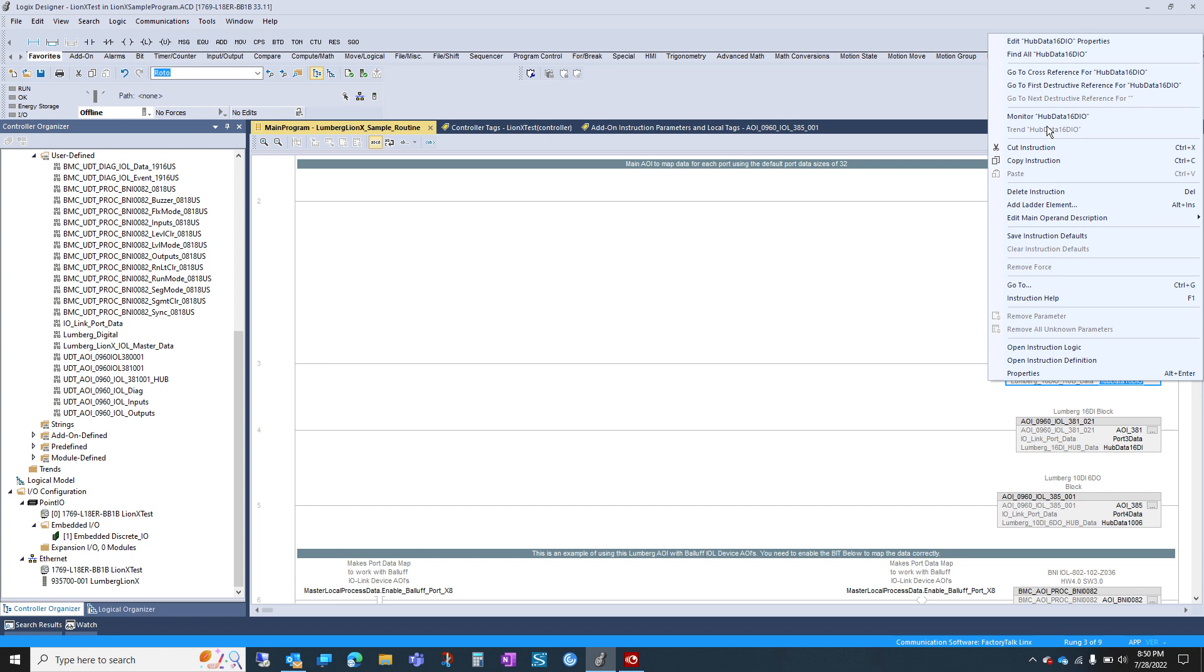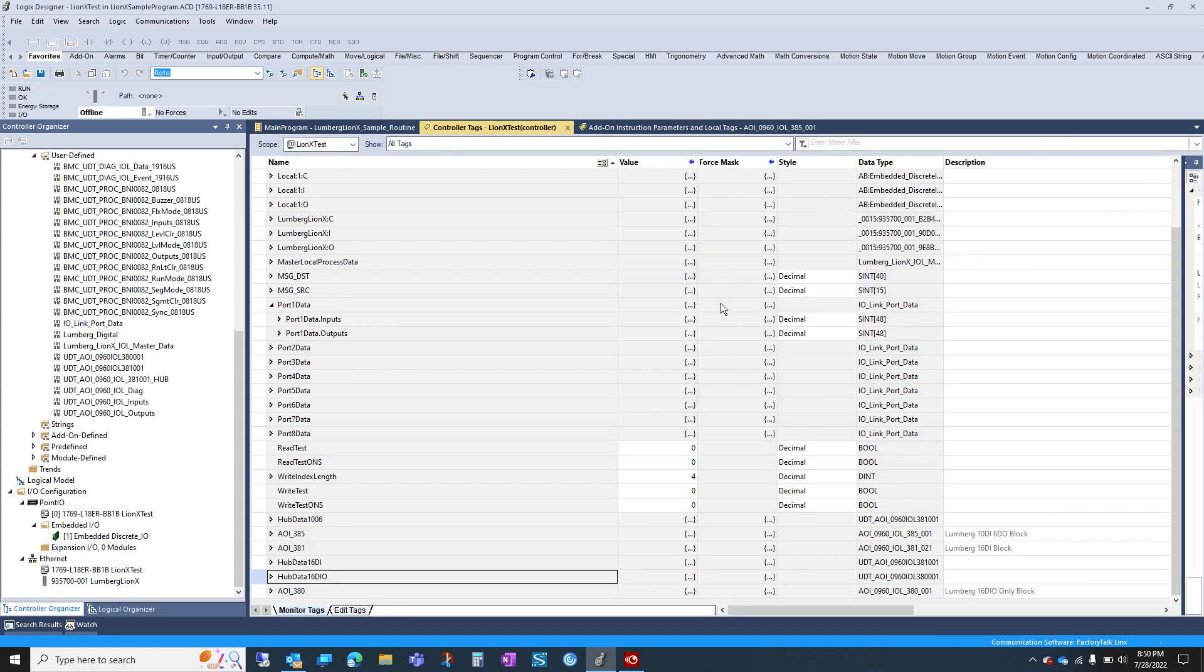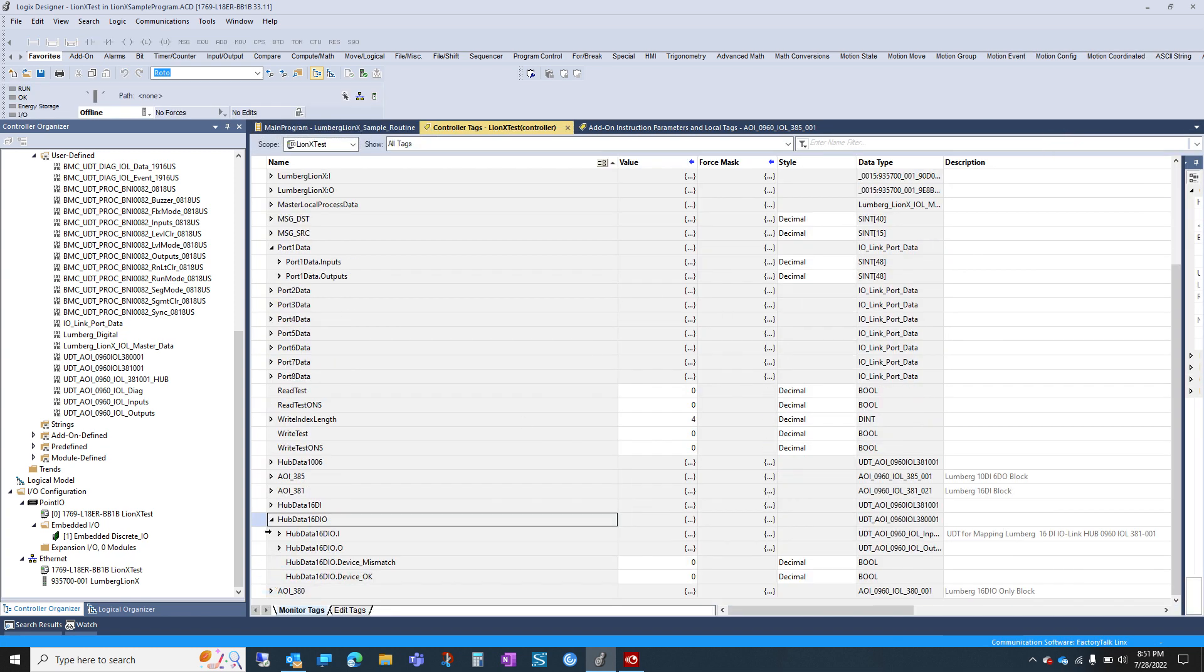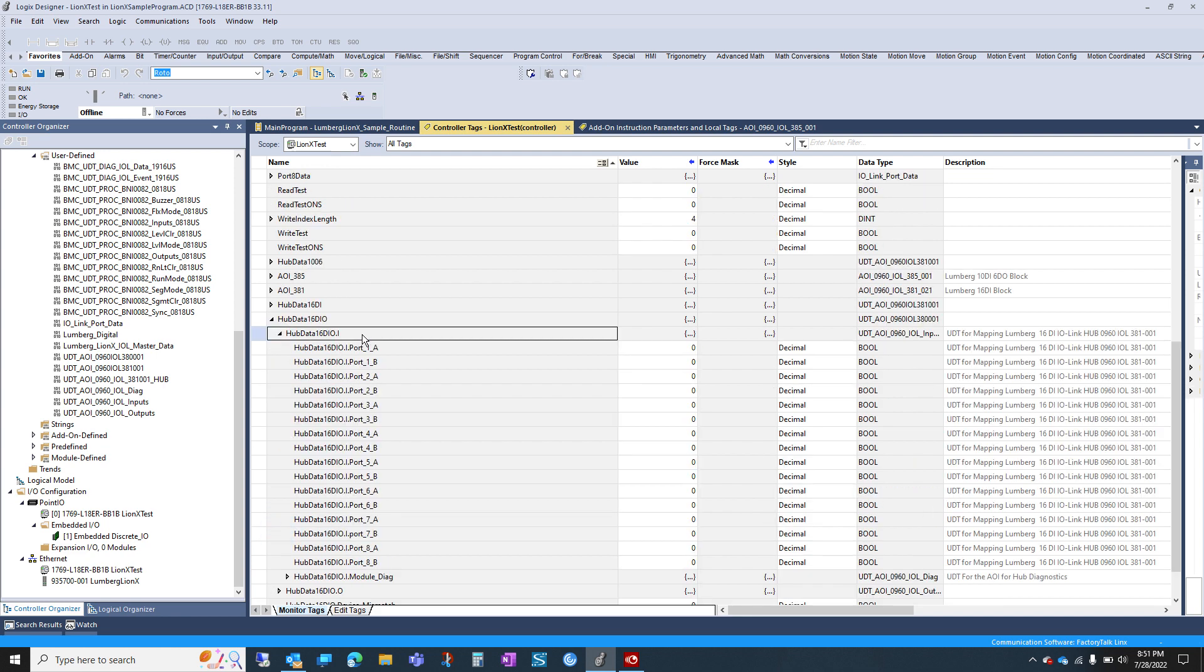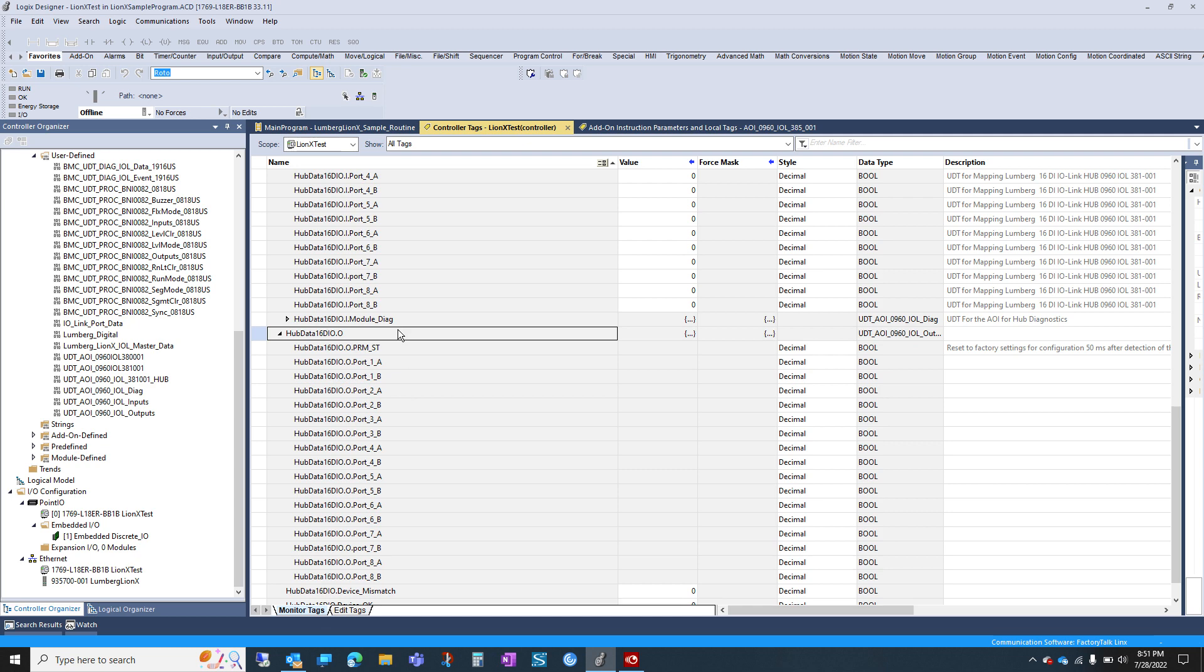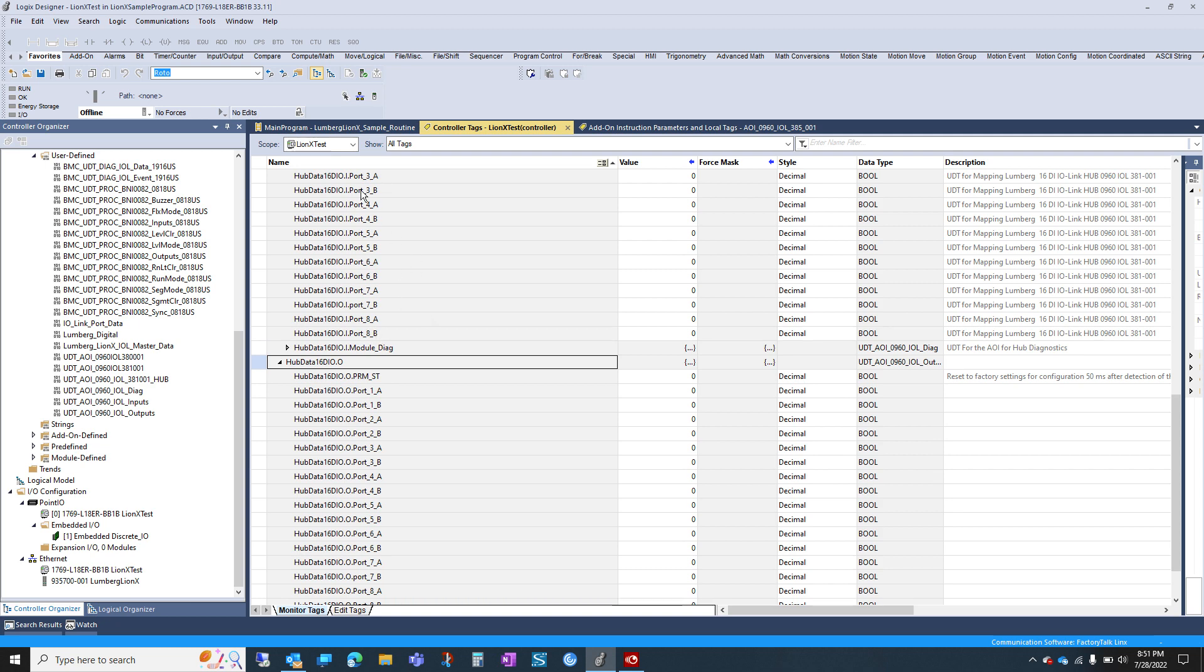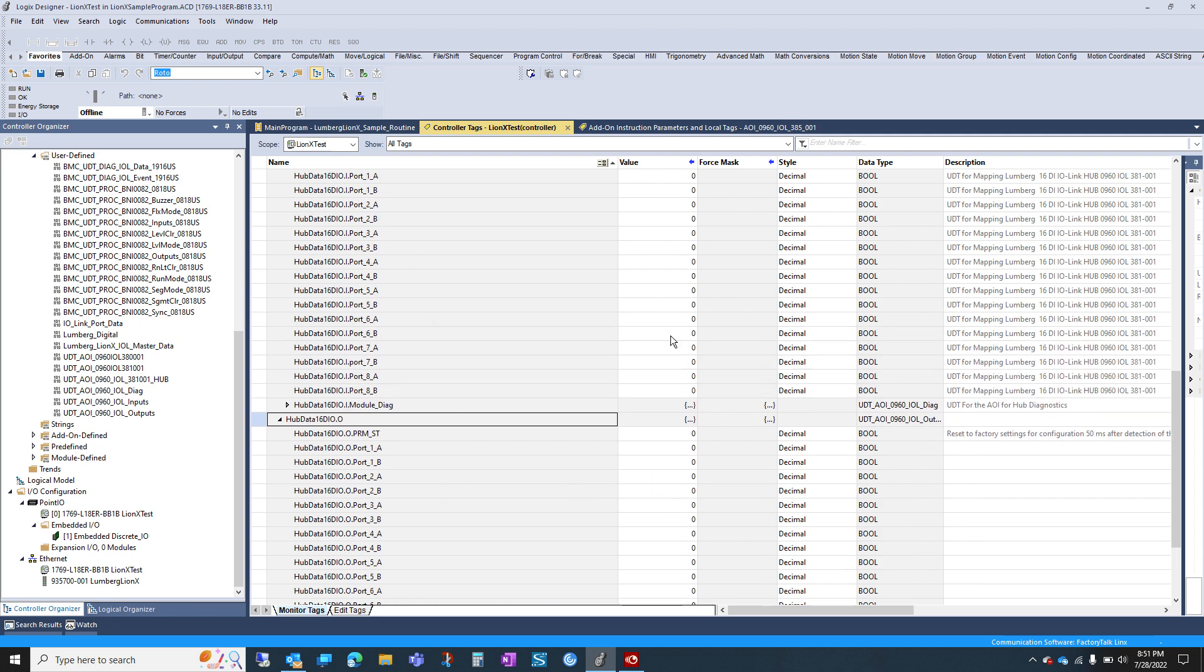So if I go look here, this is my UDT for the hub. So instead of raw data, now I actually have my digital inputs and outputs. Port 8 digital input, port 1 digital in A side, B side, all the way down. And same with your outputs, along with some additional statuses. So you don't need to, you know, you can just fire the output to treat it as an output or use the input.